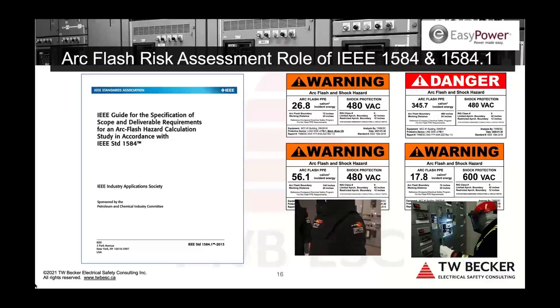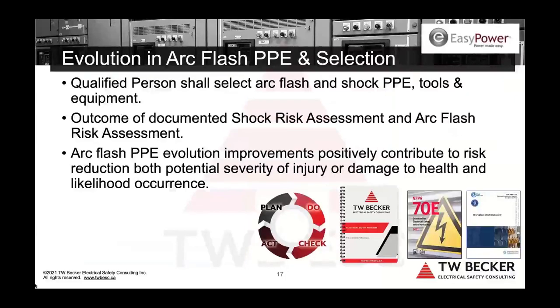So evolution of arc flash and shock PPE and selection, right? So Jim alluded that I bring this in my presentations. It's important to understand what's going on here, and it's still not out there. There's still not an awareness of all the good things that are happening to arc flash PPE. So the outcome of the arc flash and shock risk assessments are the selection of PPE by the qualified person. The evolution improvements, again, some of these have been around for years, still not known. Some of them are fairly new, all right? The escape strap option, all right?